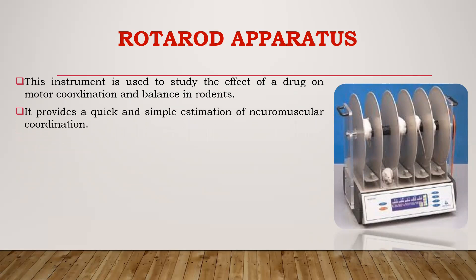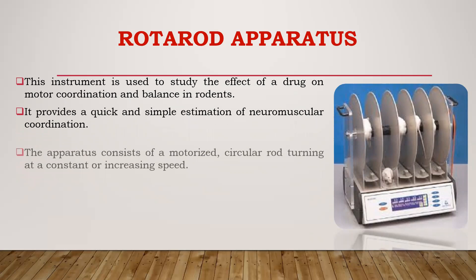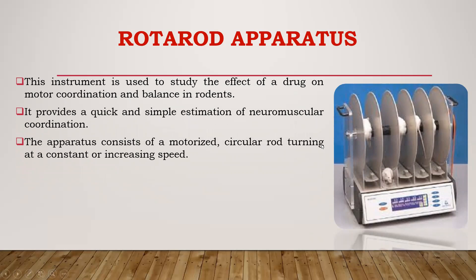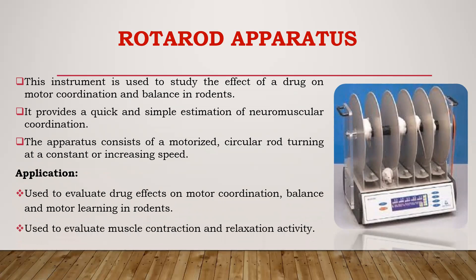Then there is the rota rod apparatus. This is used to study the effect of a drug on motor coordination and balance in rodents. It provides a quick and simple estimation of neuromuscular coordination in animals. The apparatus consists of a motorized circular rod rotating at a constant or increasing speed. The animal is placed on this rod and the fall-off time of the animal is noted, which indicates muscle coordination activity. It is used to evaluate drug effects on motor coordination, balance, motor learning, and muscle contraction and relaxation activity in rodents.